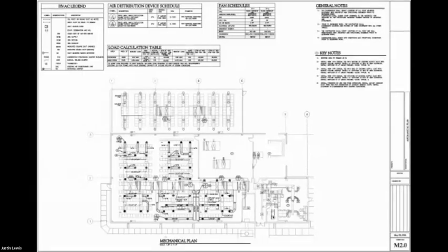So this is an existing data floor that had been having issues for quite a while. They were having hot and cold spots in the cold aisles. They weren't able to really maintain a stable temperature throughout. The owner had an in-house commissioning team, and they were working with an engineering group on plans to remodel this to take care of the problem. They were going to replace the units, upsize them, and increase the duct size to accommodate more airflow.